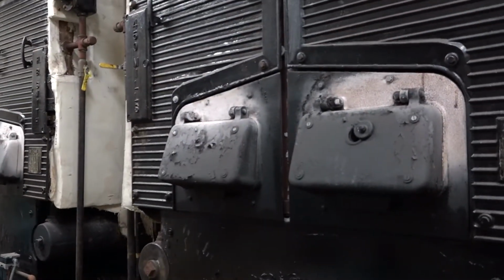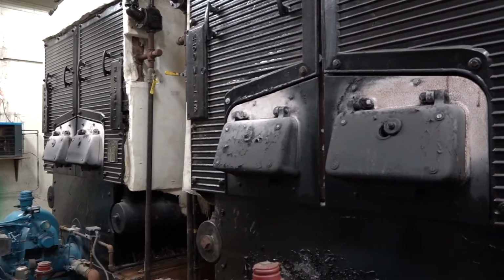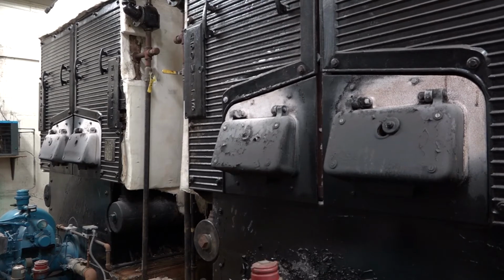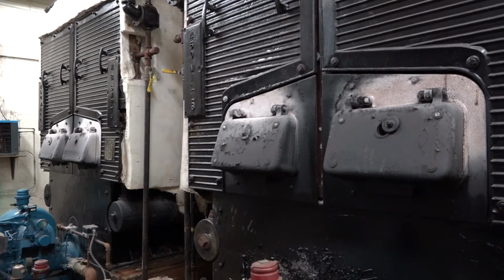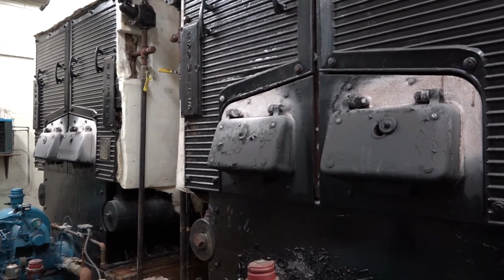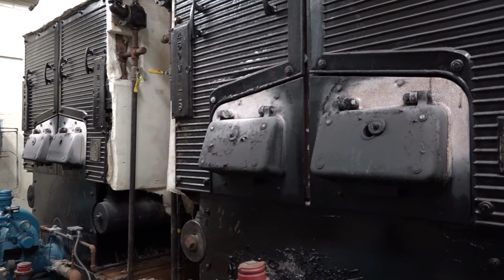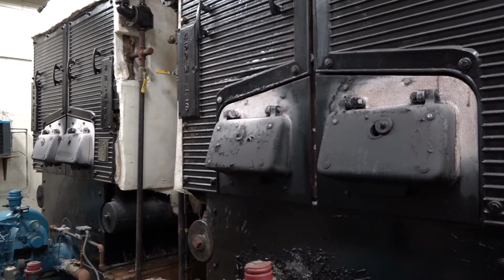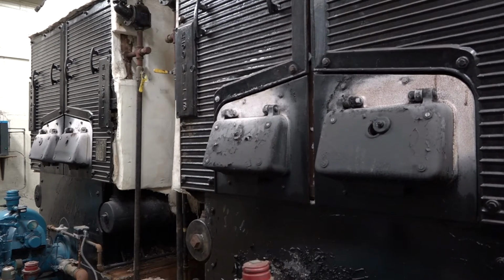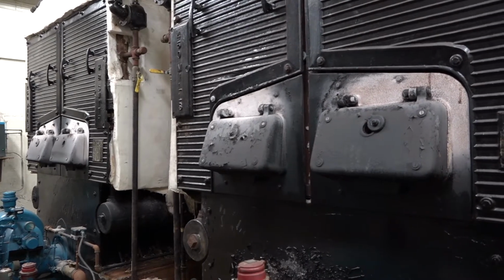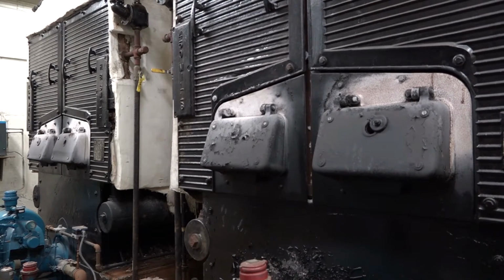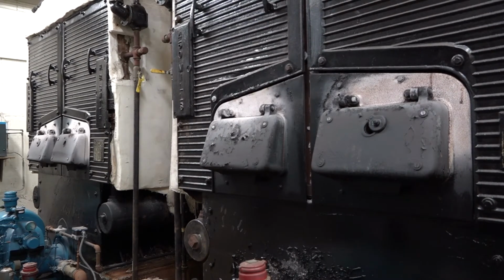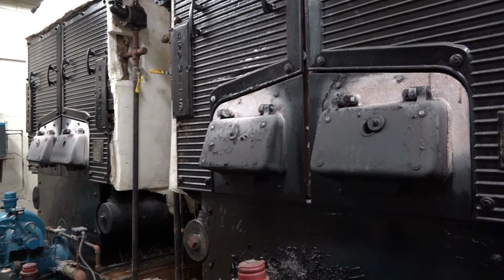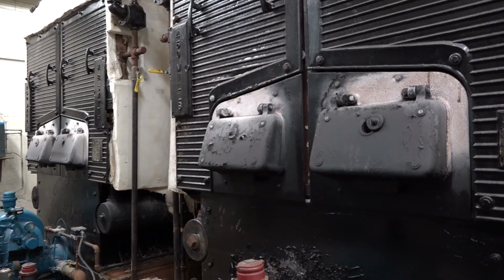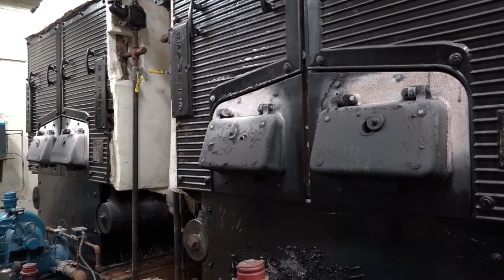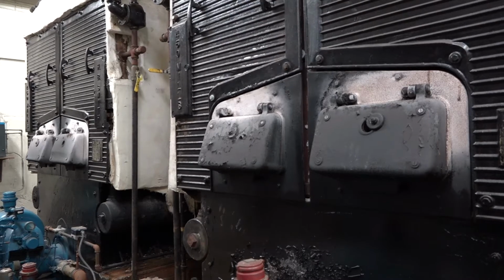All right, so these are the original boilers, 1952. Right now, we've got one that's offline because one of the mud drums on the side is rotted, and we cannot get one anywhere. The manufacturer was making them prior to the pandemic, but they fell behind on manufacturing, and we just can't get one. So we're going to try and get by on one boiler this winter, for the remainder of the school year, which shouldn't be a problem. But they're cast iron steam boilers.